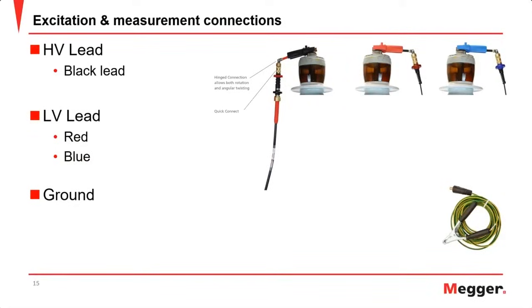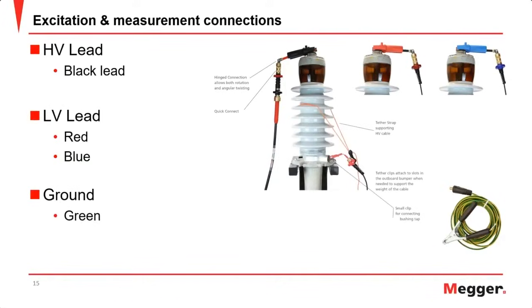When it comes to bushings, and for the high voltage bushings that we'll be talking about today, those bushings will come with a tap off the side. And the leads that we have allow you to conveniently connect to the bushing tap by disconnecting the big clamp that we have on top that goes to the top of a bushing, and using a banana plug to connect onto either the spring or the stud that is within that bushing tap.